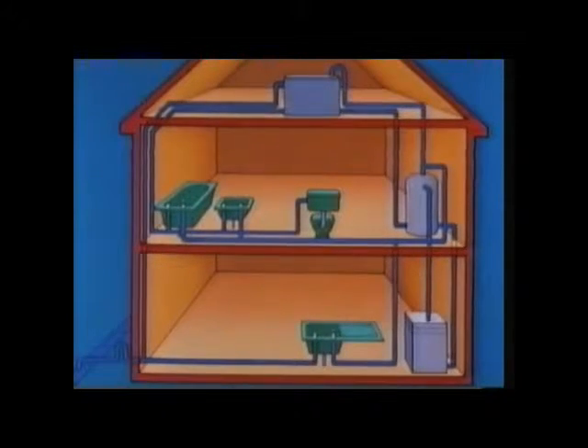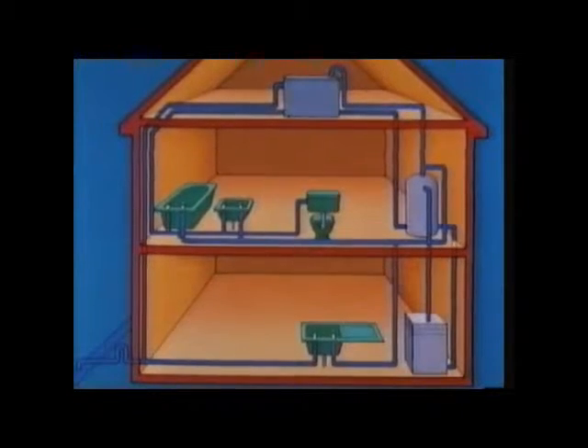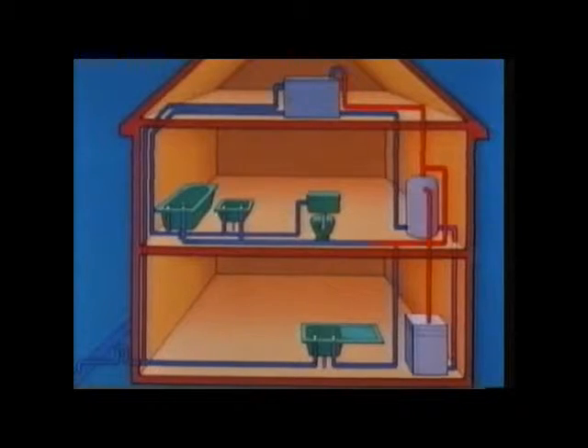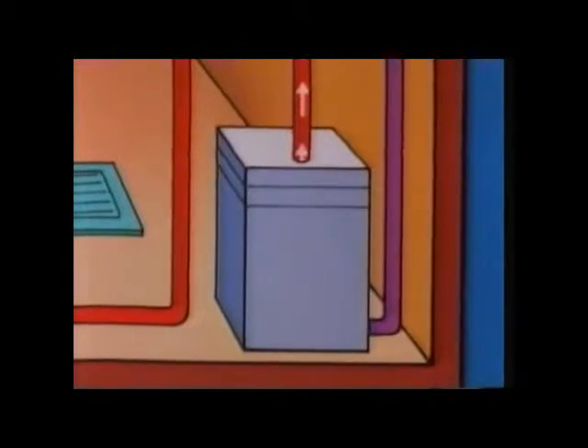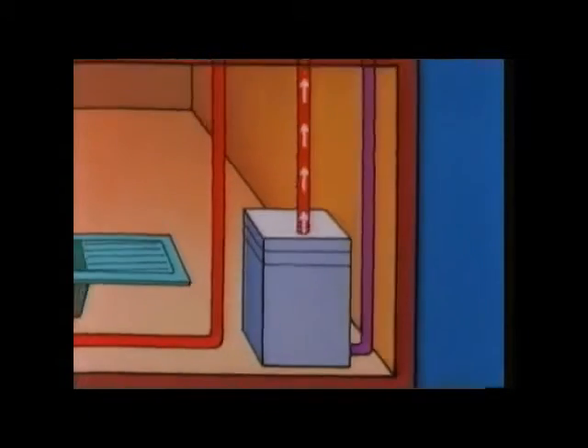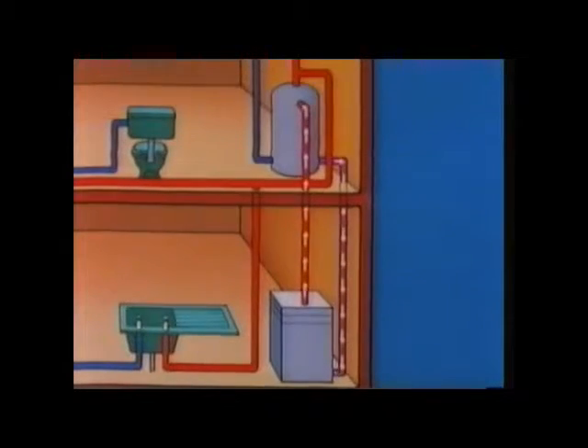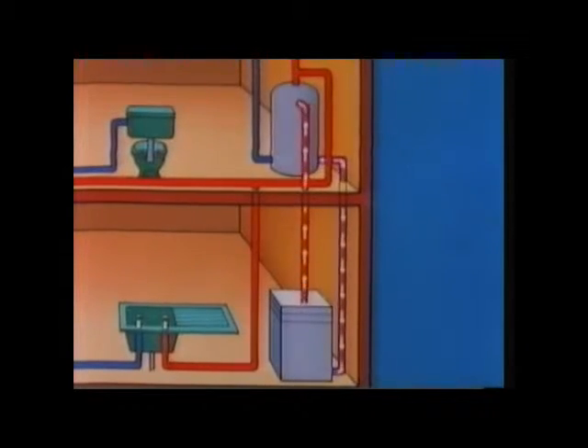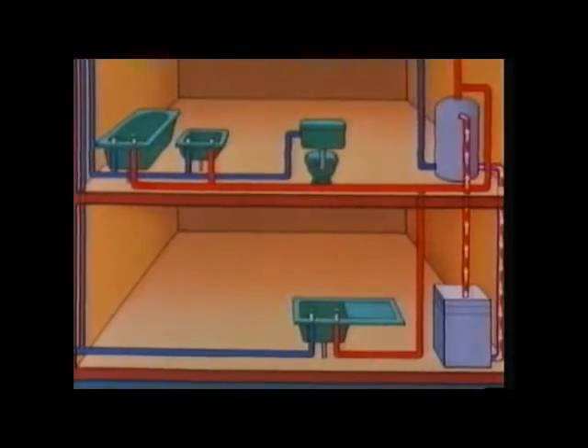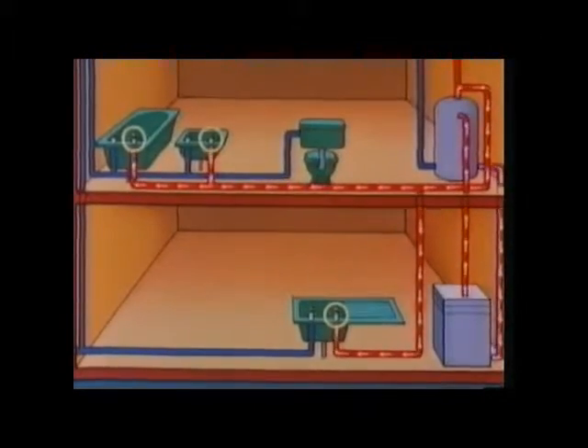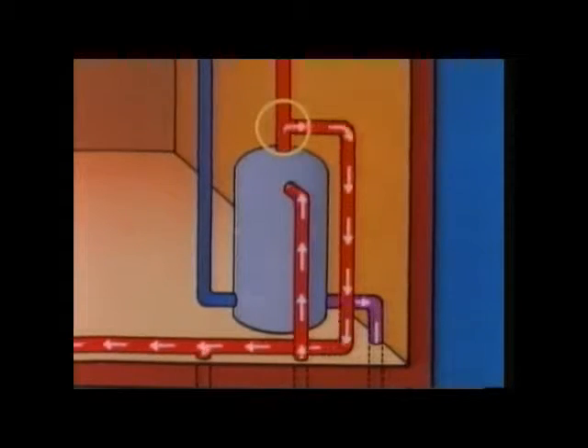Convection currents are an important factor in the design of the domestic hot water system, providing a constant supply of hot water in the storage tank. The water is heated in the boiler and rises by convection to the top of a storage tank above. Cooler water from the bottom of the storage tank flows into the boiler to replace the hot. A continuous circulation is set up and gradually the storage tank becomes filled with hot water. The hot water taps are connected to the top of the tank where the water is hottest.